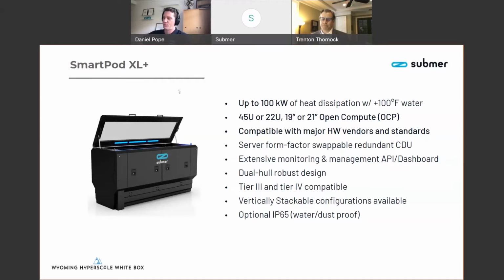It's thanks to the 48-volt bus bars that it's going to be super easy to achieve 100 and 200 kilowatts even in one of these immersion tanks. So exciting times for immersion cooling as systems get designed for the right density, where immersion obviously has a very aggressive TCO.